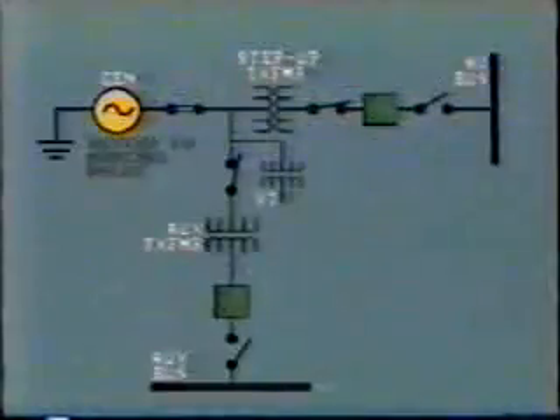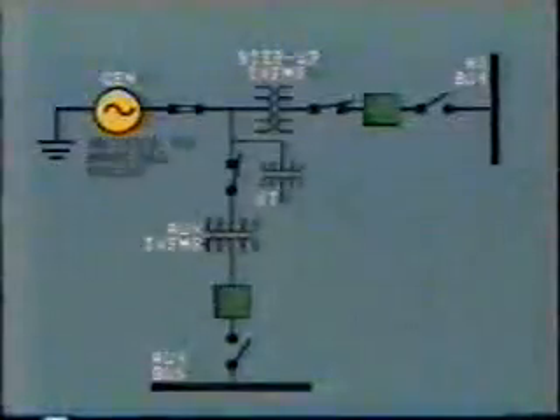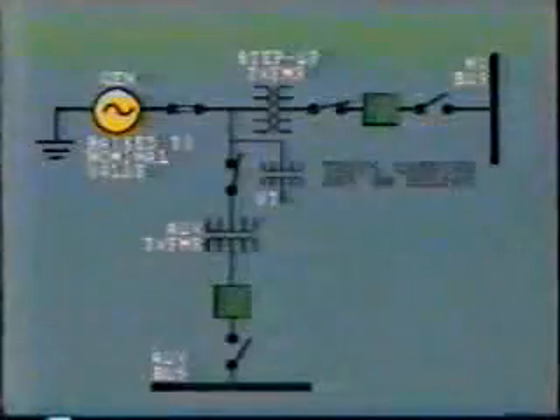Many VTs are fitted with a tertiary winding, which is connected in broken delta. Check this voltage. It should measure 0 or very low voltage. At this point, the generator terminal voltage can be raised to nominal value and voltage tests carried out on all protective relays. Clearly, before paralleling the new generator to the existing bus, we must ensure that phasing and phase rotation are identical on both sides. This may be done on the high voltage side of the unit transformer.